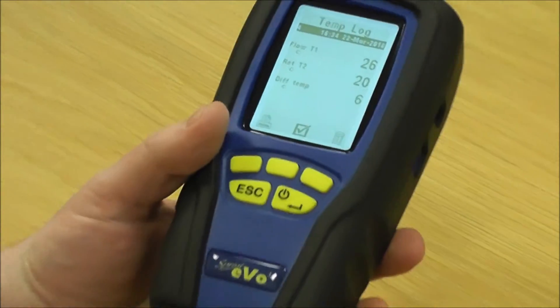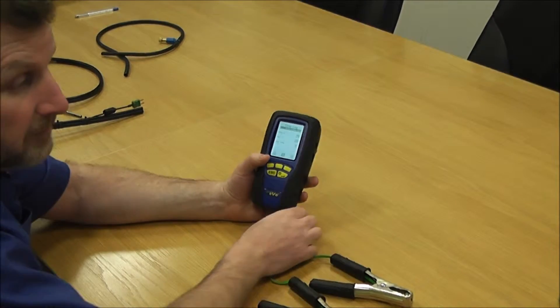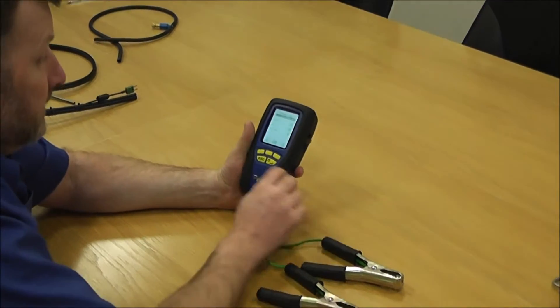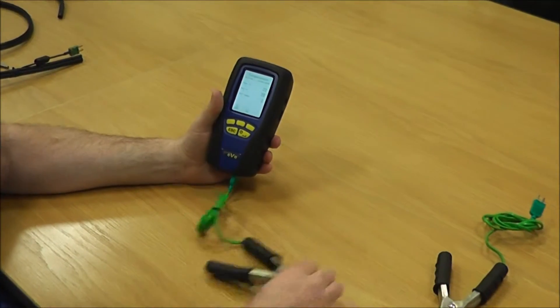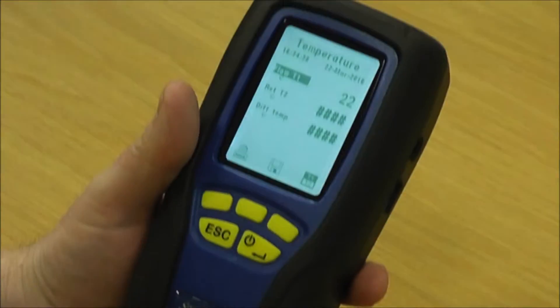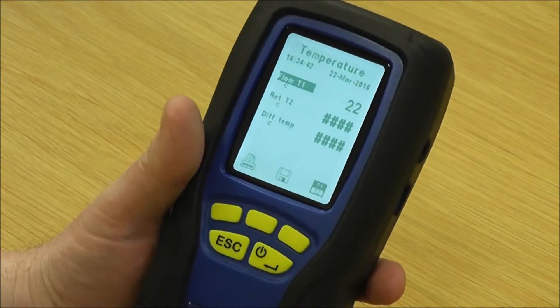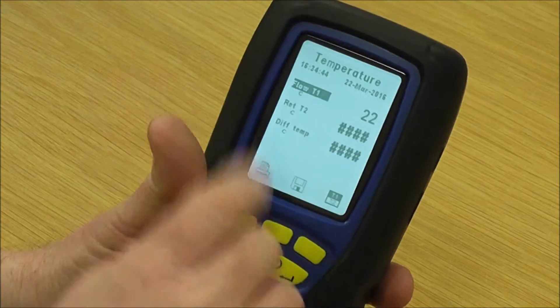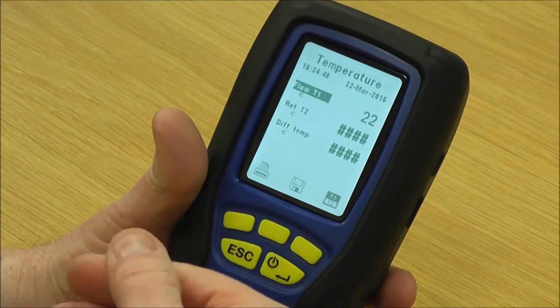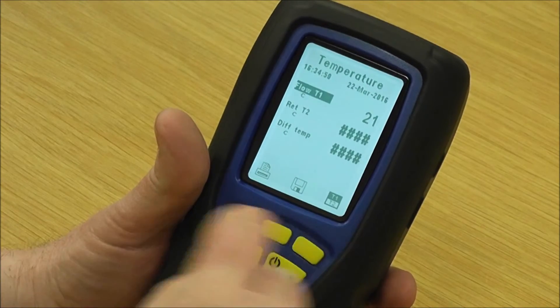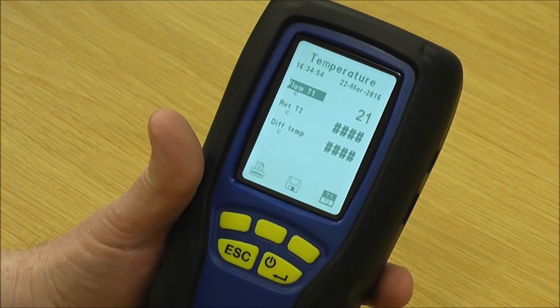You can use individual mode if you just want to do a single temperature. If you had applications like setting up thermostatic valves and you only want to do a single temperature, you can still save just a single temperature, print it out, and then write any references you want on the little printout docket that you get.